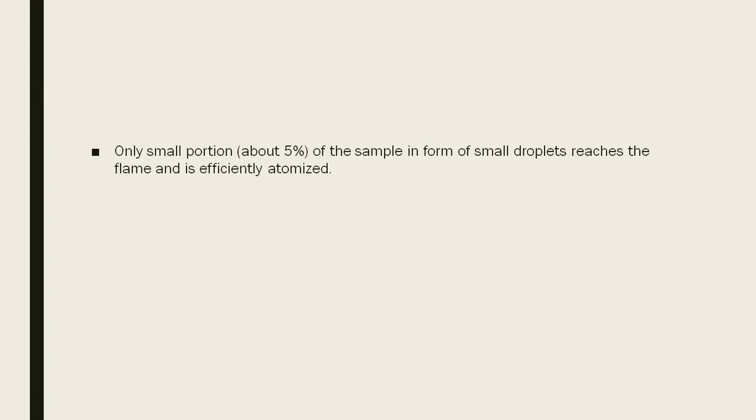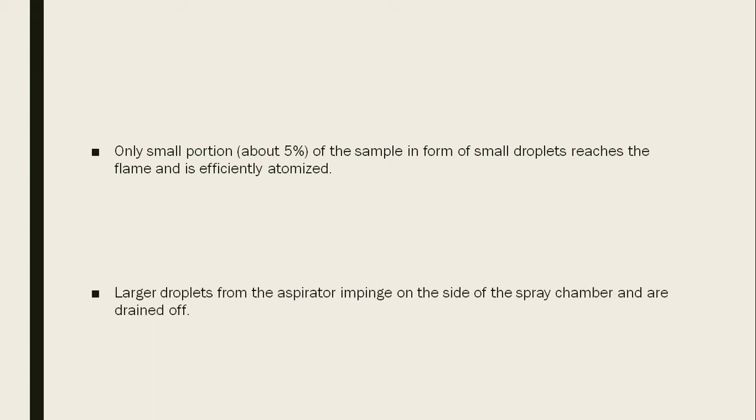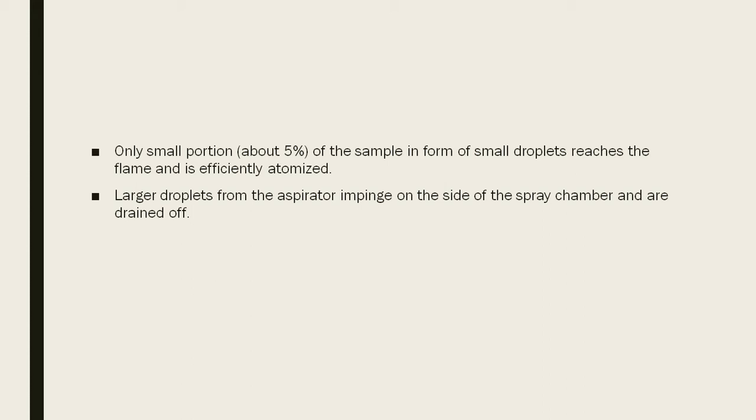Only a small portion, that is about 5% of the sample in the form of small droplets, reaches the flame and is efficiently atomized. Larger droplets from the aspirator impinge on the side of the spray chamber and are drained off. So as shown, only a small portion, that is smaller droplets, will reach the flame. Larger droplets are drained away.